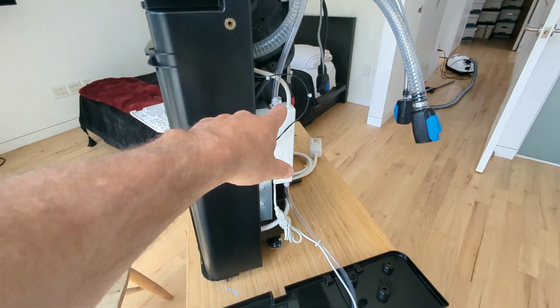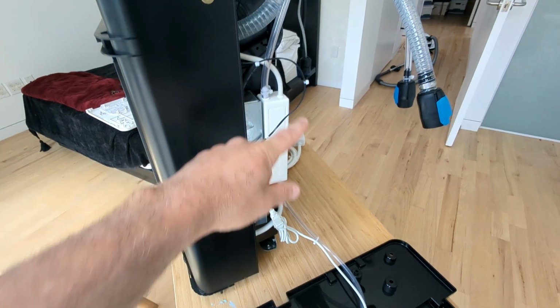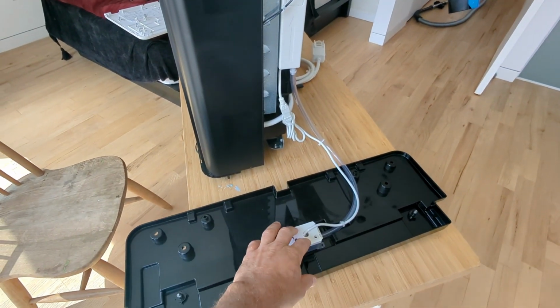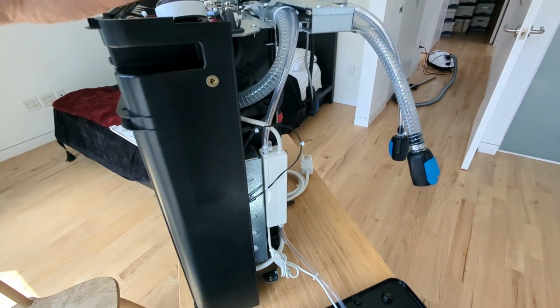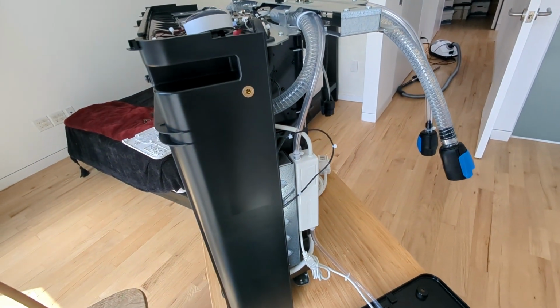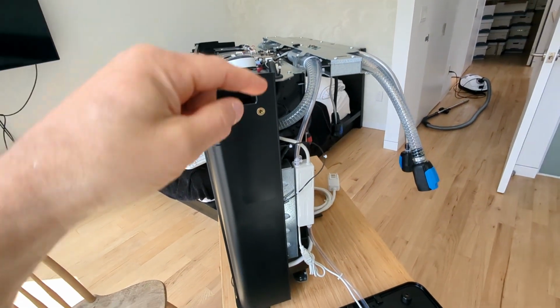Another missed opportunity here is that since this pump is triggered only automatically based on that float switch, there's no way that they can trigger it from the controller. And in fact, I don't even think the controller can tell when it's been triggered.